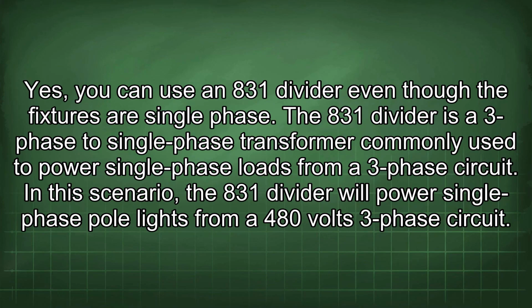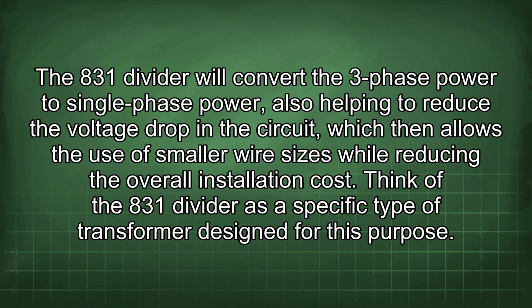Yes, you can use an 831 divider even though the fixtures are single phase. The 831 divider is a three-phase to single-phase transformer commonly used to power single-phase loads from a three-phase circuit. In this scenario, the 831 divider will power single-phase pole lights from a 480 volts three-phase circuit. The 831 divider will convert the three-phase power to single-phase power, also helping to reduce the voltage drop in the circuit, which then allows the use of smaller wire sizes while reducing the overall installation cost.